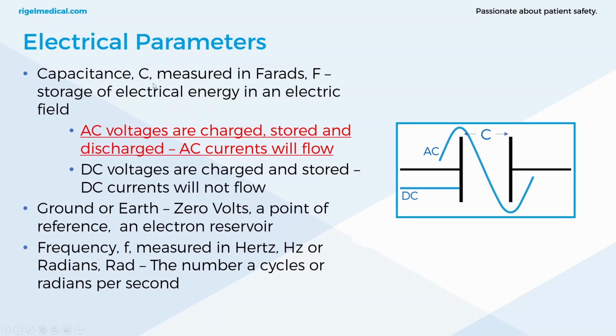There's capacitance, C, which is measured in farads. This is the storage of electrical energy in an electric field. AC voltages are stored and discharged. These AC currents will flow. DC voltages are charged and stored. DC currents will not flow. Now, AC is highlighted as this shows how electrons can flow to the casing or the applied parts or patient leads of medical electrical equipment. Then we've got ground or earth. This is the 0 volts point of reference, and it provides a path for electrons to flow in the case of faults and leakage currents. Frequency, F, is measured in hertz. This is the number of cycles or radians per second.